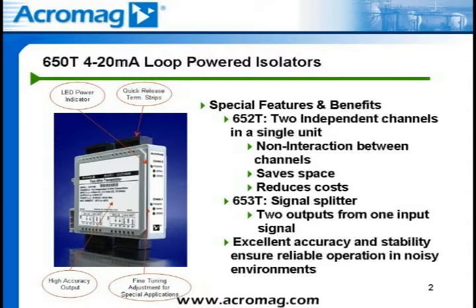The 653T module can be used to retransmit an analog input signal over two independent and isolated output loops to prevent interaction, provide power supply isolation, and eliminate potential ground loops.